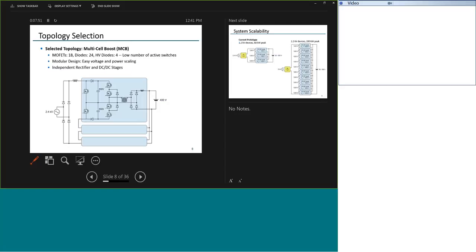This is the actual topology we selected. We have a low-frequency full-bridge diode rectifier, followed by a multi-cell boost used for power factor correction, then a DC bus, and then a DC to DC converter. To deal with the high input voltage, we series connect three such modules. To deal with the low voltage and high power on the output side, we connect all the modules in parallel on the output side. And we rely on the high frequency transformer for isolation.